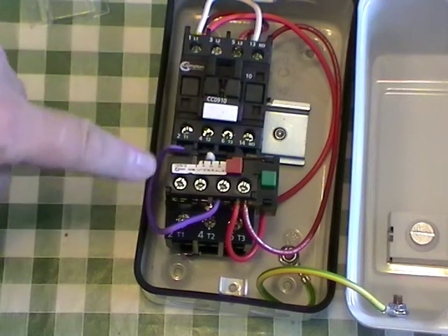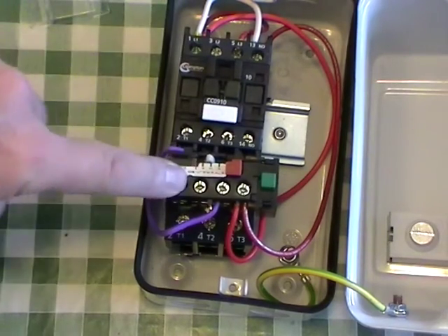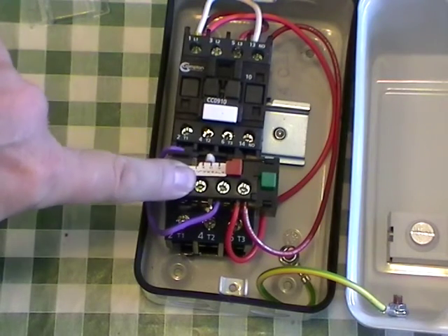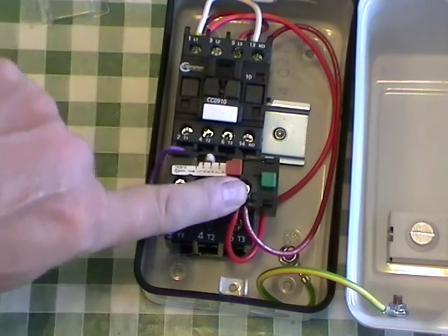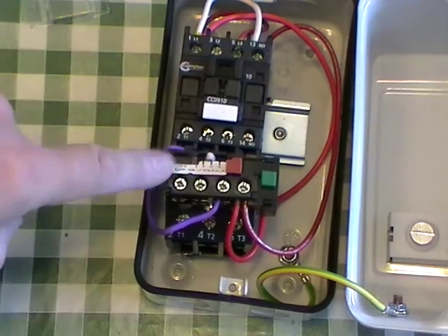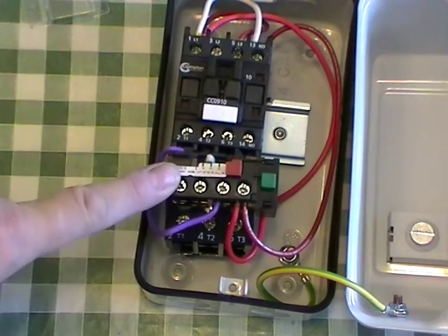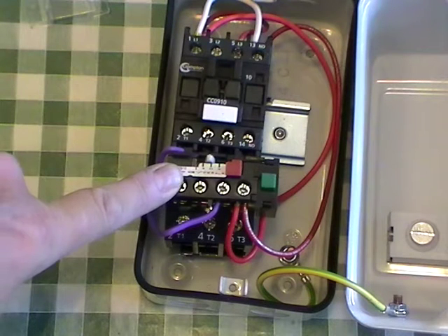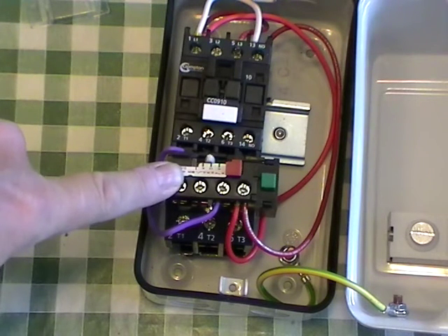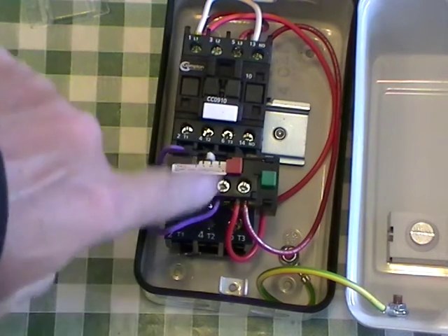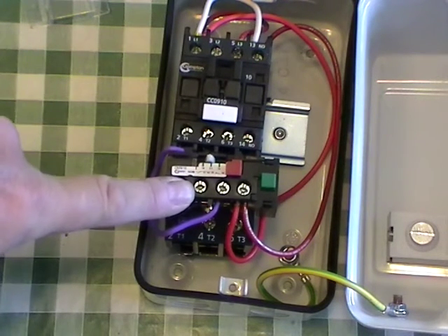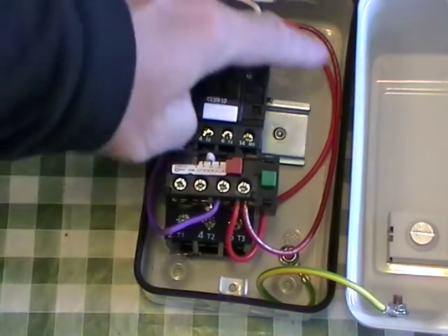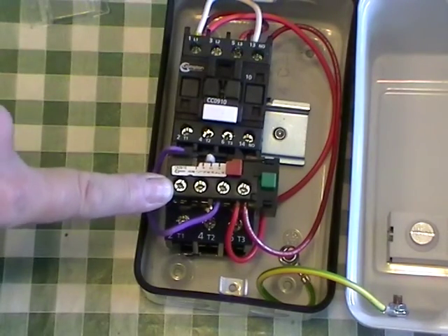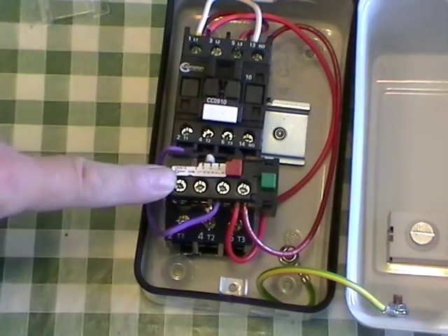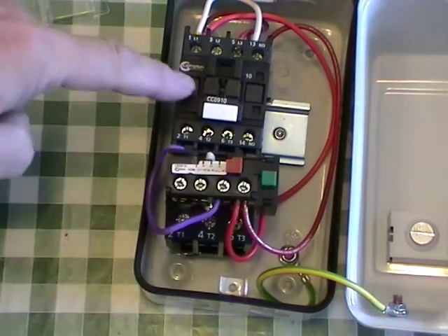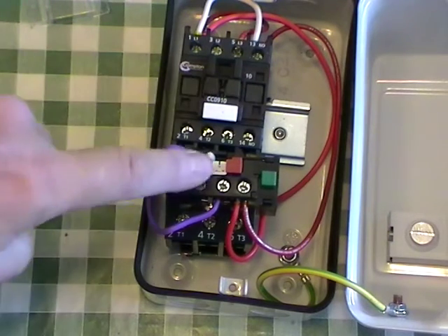Normally the power to the green button goes through the trip, so that if it trips out, the green button also does not work, so you cannot attempt to restart it while the trip has activated. For the reason that this generator has limited output, I don't need that protection. So I've reconfigured the existing wires. All these wires were in this box when I got it, but I've rearranged them so that the green button will always switch the motor on, irrespective of the trip.